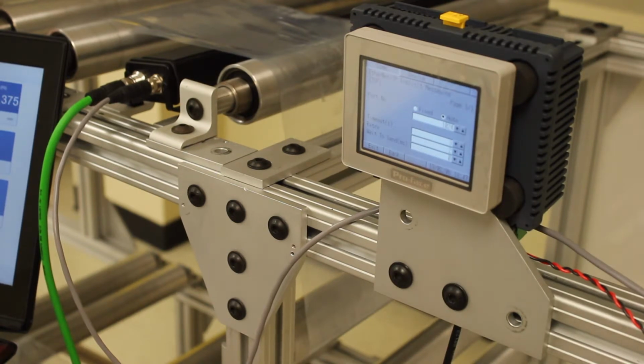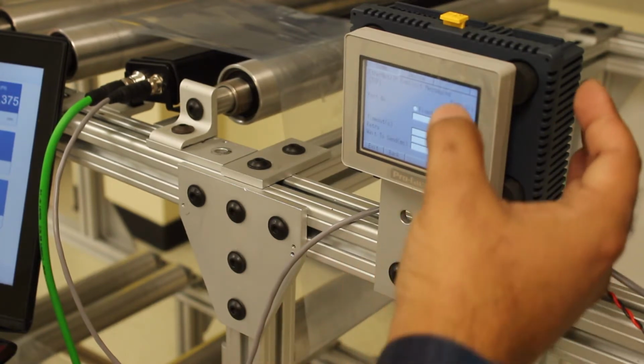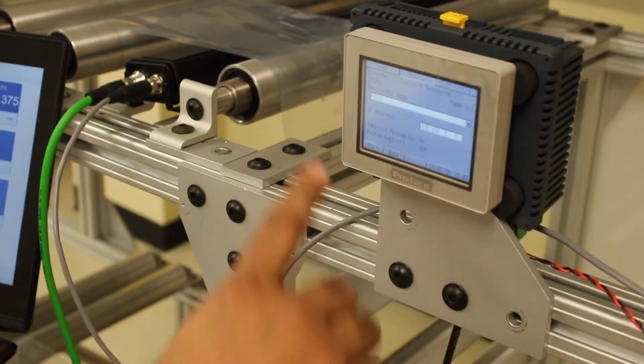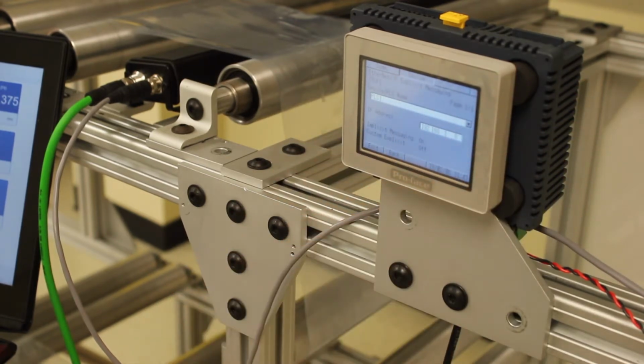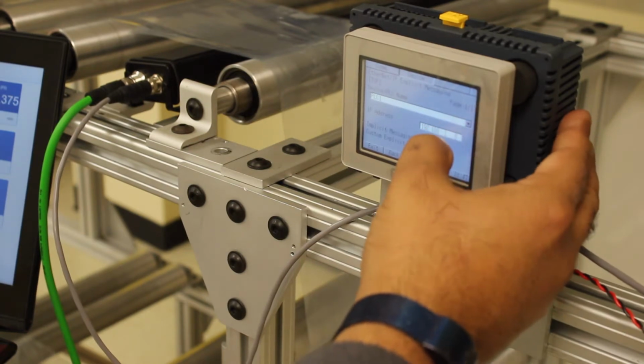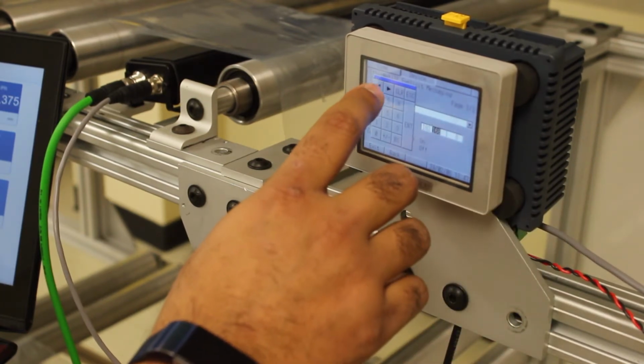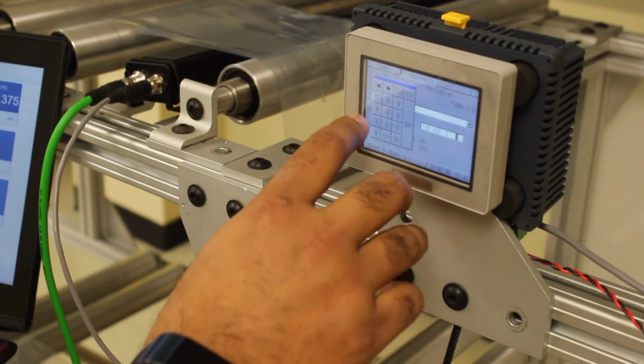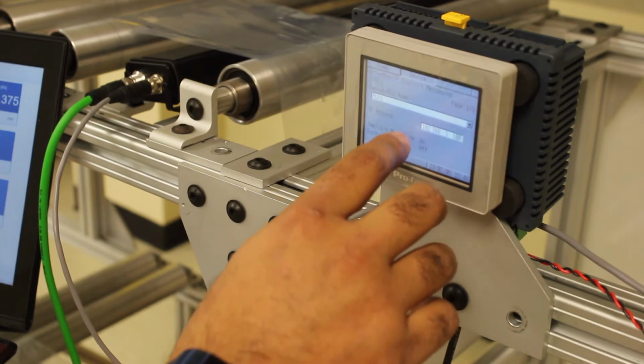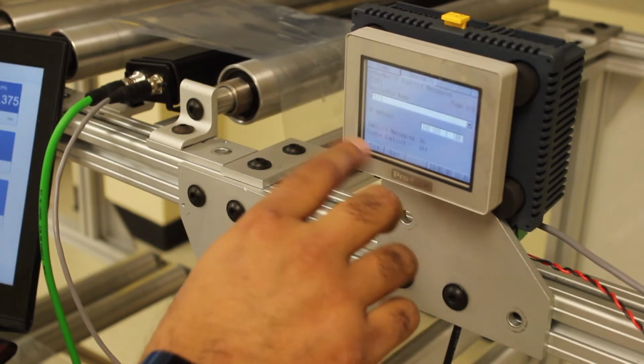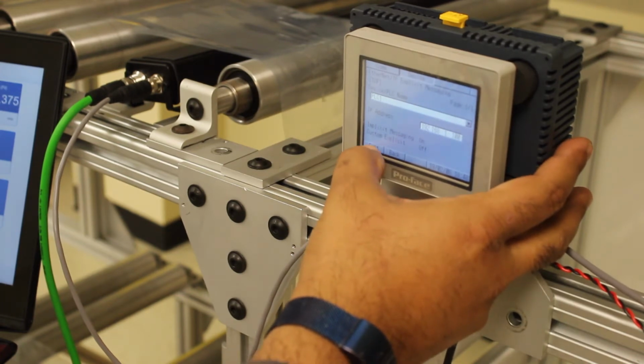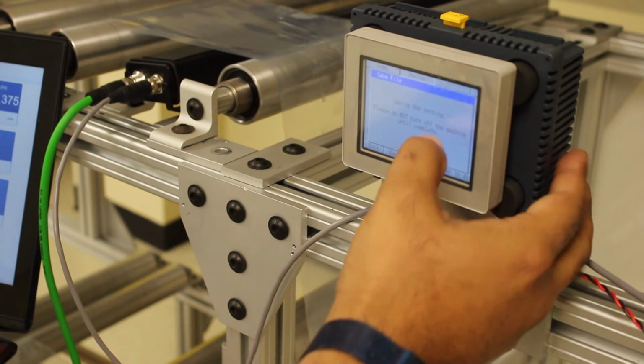So that's the one we're going to select. These settings are fine, which is the standard setting. The main thing that we want to set is the IP address of the device. So we click on device and then set the IP address. Right now it's set to 192.168.1.8. Our sensor IP address that we manually set was 192.168.1.100. So we're going to type in 100, enter, exit, and then save changes. Now the PLC is going to reboot with the new IP address.